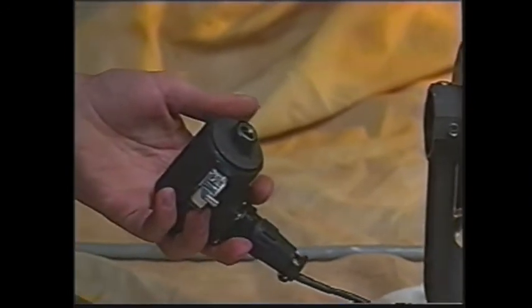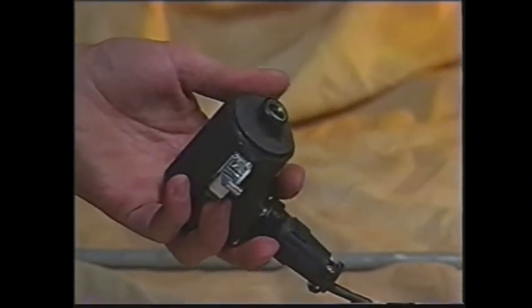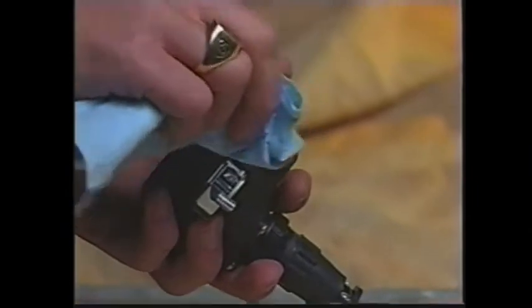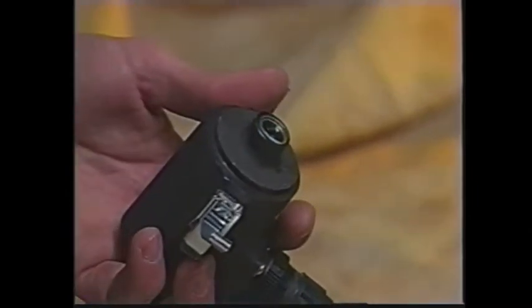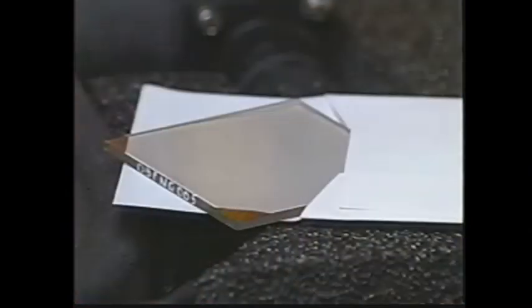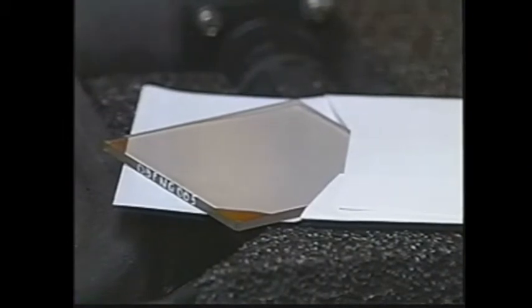It is very important that the lenses are cleaned regularly. It assures accurate test results. Snap off the closures. Wipe the lenses with a soft cloth. We recommend regular checks with the calibration filter.